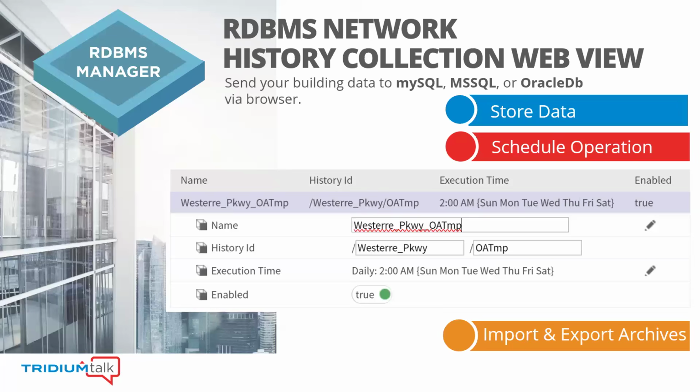Now the problem being solved essentially is that if you keep them locally, you're going to grow the size of your local alarm and history databases. Now, if you've had the Niagara framework installed for years and years, what you will quickly find is that you've got millions of records that are just housed within those local alarm or history databases.